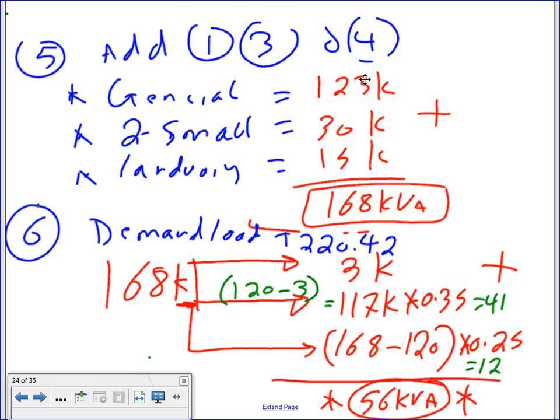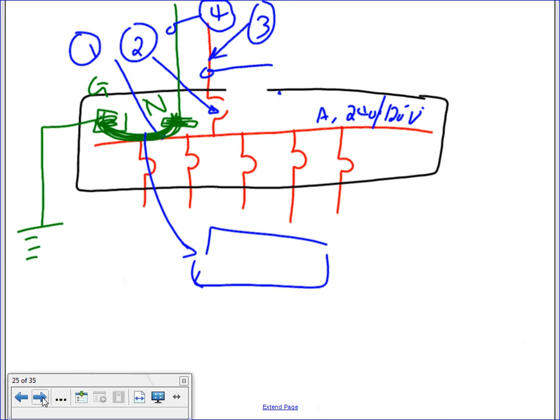Okay, let's go to the next step. By the way, this is what we're sizing, guys. We forgot to tell you what you need to size. You will be required to do the overcurrent protection device, the service size, the neutral and the main bonding jumper. That's what you're required to size at the end.